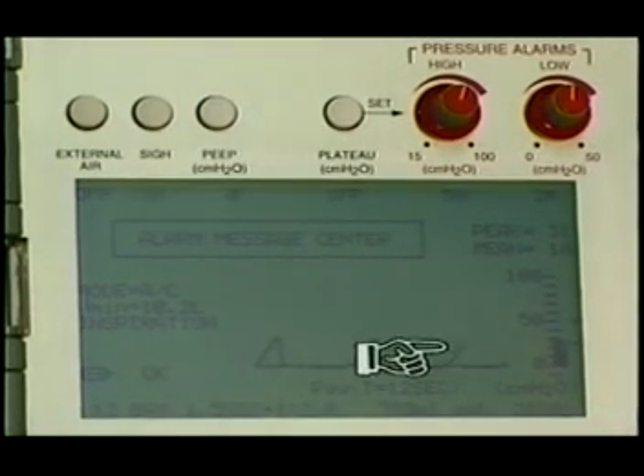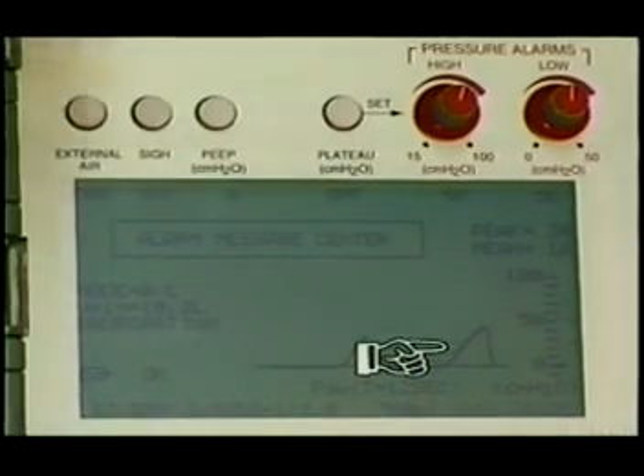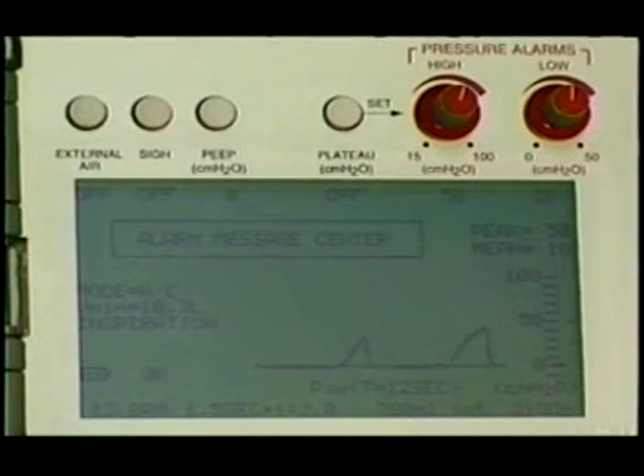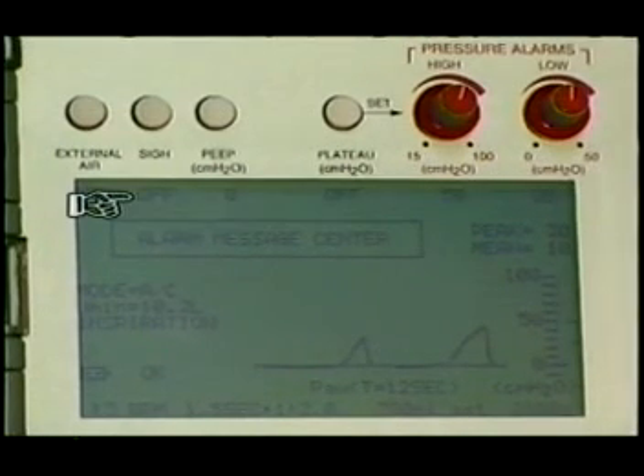The SIGH off-on push button switch has a default value of off. When set to on, the first breath delivered is a sigh. Each sigh breath is 150% of the inspiration time setting, which increases delivered volume by 50%. The sigh breath is repeated once every 100 breaths or 7 minutes thereafter, whichever occurs first. Sigh status, off or on, is displayed in the LCD beneath this push button switch. Sigh is disabled when pressure plateau is on.